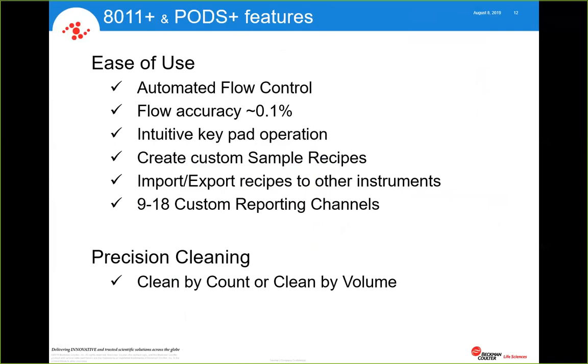If you need some other channel sizes, then it's very simple to create a custom reporting standard within the application, and it will actually determine via interpolation what the threshold value is for your particular size. If you need an interim size in between, say, 4 and 6, just for your own edification, you're able to do that, and the instrument itself will provide that for you automatically internally.